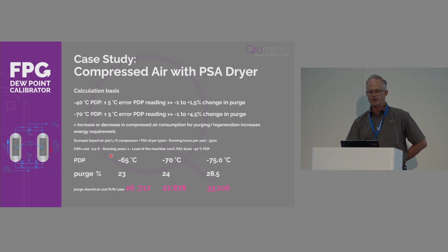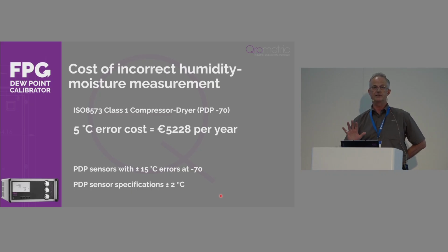Now, the cost of running a typical 300 liter per second industrial compressor is around 26,000 euros per year if you are working with a pressure dew point of minus 65. At minus 70, 28,000 euros per year, and at minus 75, 33,000 euros per year. So it's 33,000 euros just to run that dryer to maintain the pressure dew point. And minus 75 is a critical value for class 1 air dryers. So we made the calculation that if you have a 5-degree error in the measurement of pressure dew point in a compressed air system, the cost of that error for one dryer is 5,000 euros per year.